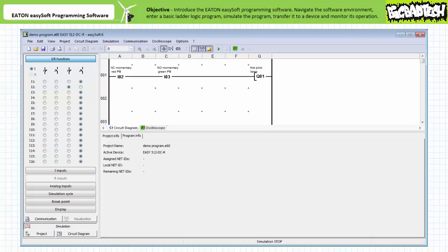Start thinking now how output Q1 should respond to four different input scenarios. One: when both simulated field input devices are in their deactivated states. Two: when only the normally closed red push button attached to input I2 is actuated. Three: when only the normally open green push button attached to input I3 is actuated. And finally, four: when both buttons are actuated. If you're tracking, you should anticipate output Q1 to be asserted when only the normally open green push button attached to input I3 is actuated. Let's see if the simulation verifies our hypothesis.